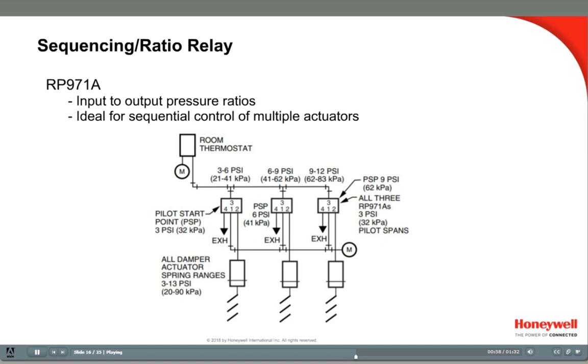In this application, 3 dampers are staged to open using 3 RP971 relays, each with 3 psi spans. The first sequencing relay is set to 3 psi, so as the branch line from the thermostat rises from 3 to 6 psi, it sends a 3 to 13 psi signal to its damper. Then as the branch line rises from 6 to 9 psi, the second sequencing relay opens its damper with a 3 to 13 psi signal. The third sequencing relay operates as the branch line increases from 9 to 12 psi.